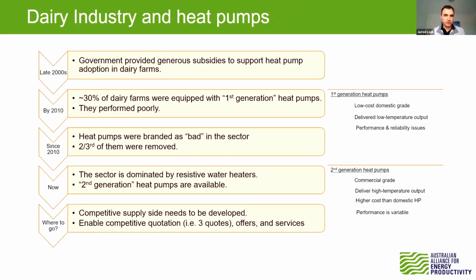There was a big push on heat pumps in the late 2000s, and it was adopted quite widely, up to maybe 30% of the dairy farms in Victoria. However, it was not a pleasant experience for most. They were often domestic or residential grade heat pumps, and there were a lot of failures and problems with those. From what we understand from our research, at least 2/3 of those have been removed from dairy farms, and it does have a bad name, that these lower quality heat pumps that went in there really weren't fit for purpose. Some people had really nice clean water and clean conditions, and they've survived with their heat pump and they love them, but unfortunately that was not the majority.